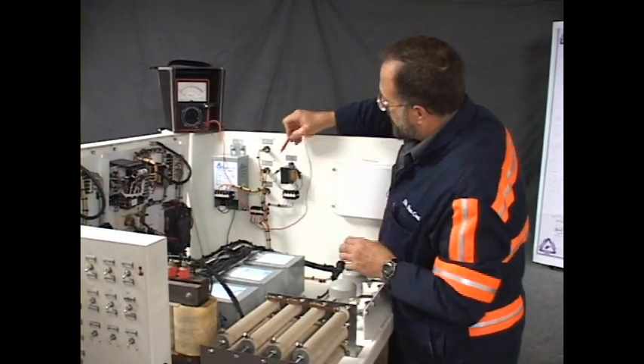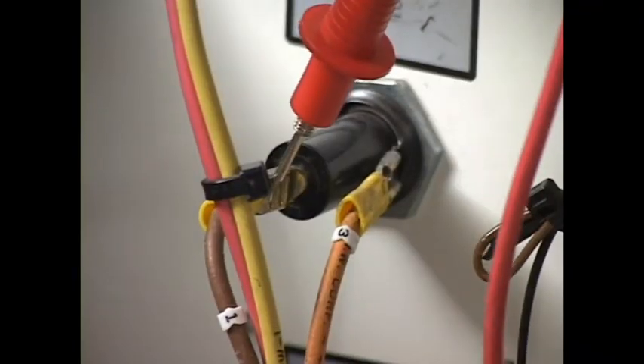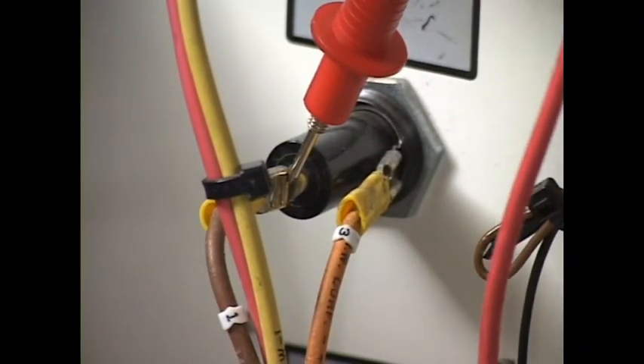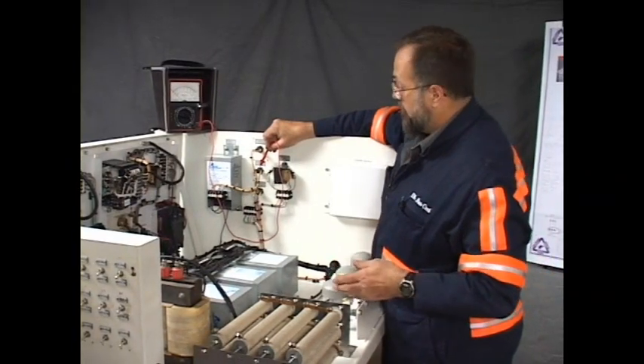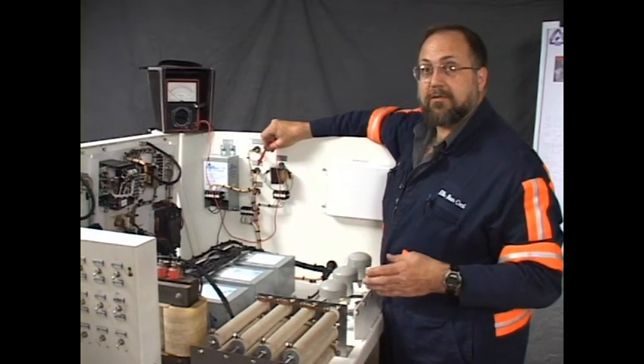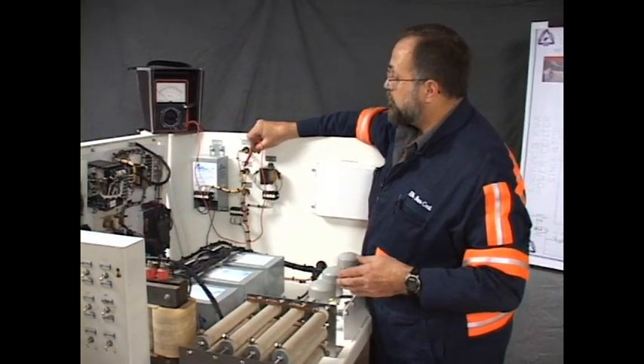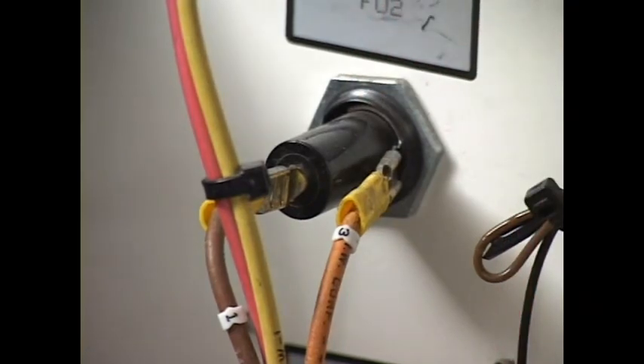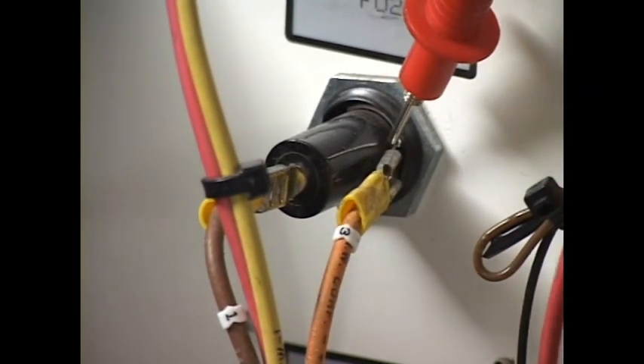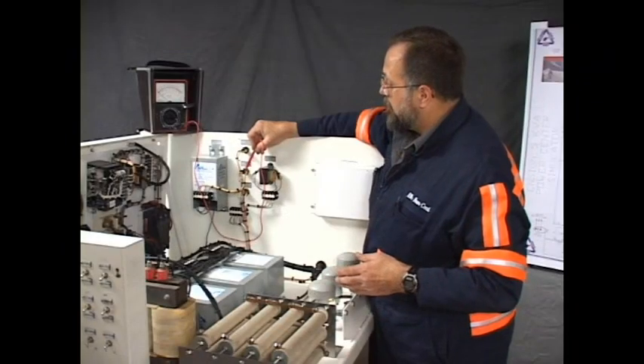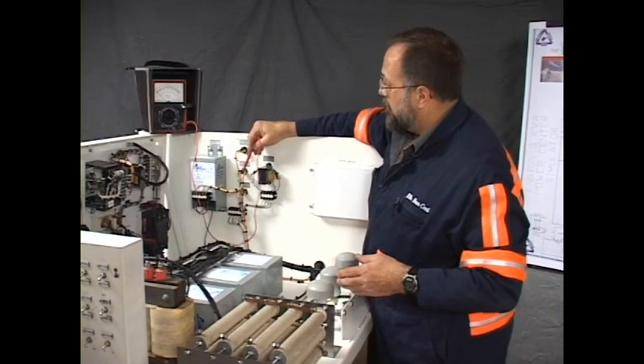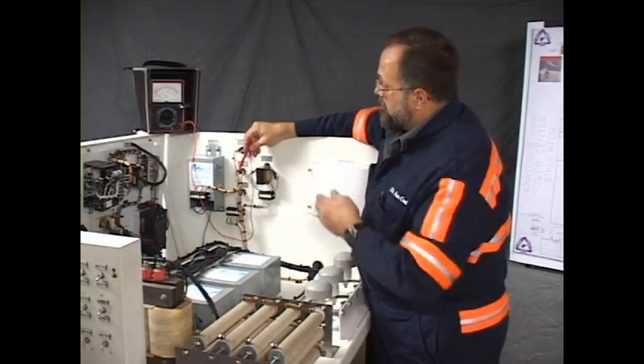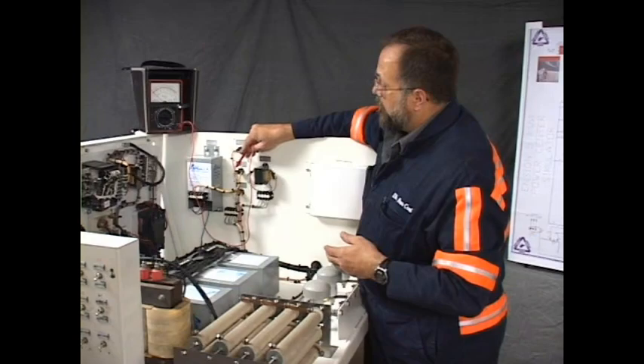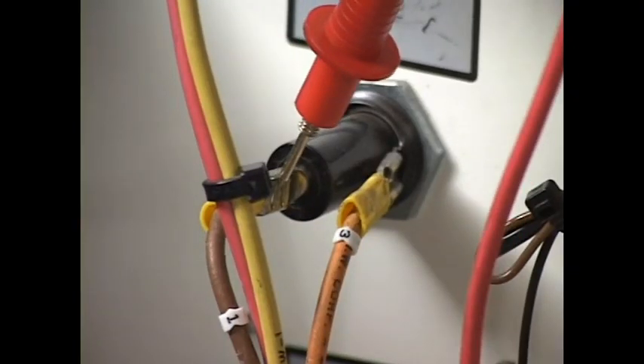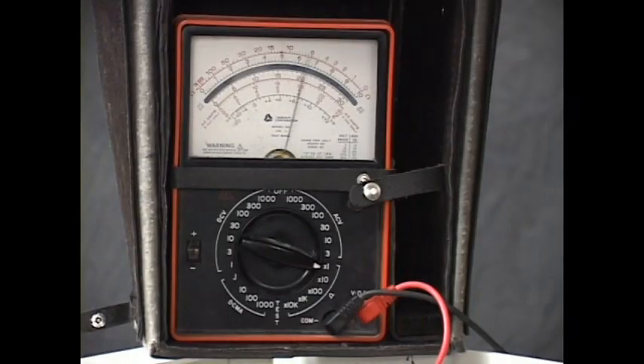This fuse is located here. Wire number 1 is marked with a marker. On this type of dash mount fuse, usually the line side, or the side toward the source, is attached to a rear terminal. The terminal on the side is usually the load side, but the wires are marked and are also color coded, so that won't be an issue finding our way. With one lead attached to one end of wire number 1, I'm going to put the probe to the other end, and as you can see the needle movement, it reads 0 ohms resistance.